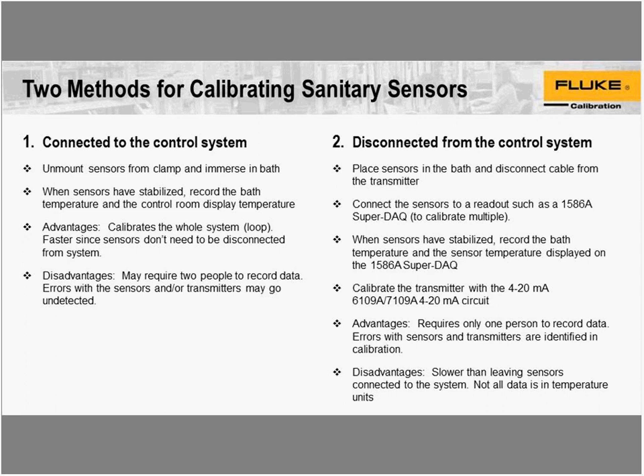The advantage with this is it's a very simple method where the whole system is calibrated. The display and the sensor both are calibrated as a system, or as a loop, and you don't have to disconnect any cabling from the system. The disadvantage is that it may take two people to do the calibration, because you may have to have one person in the control room monitoring the display and feeding back to the person out at the site with the temperature sensor.